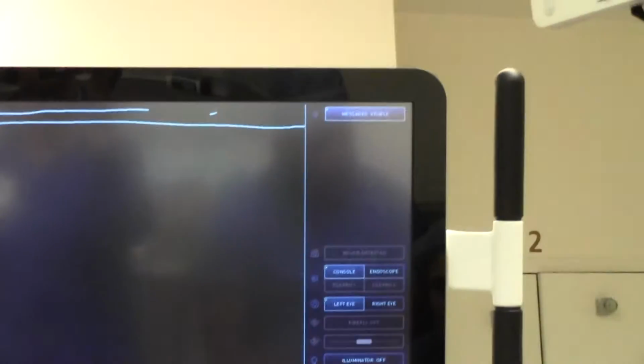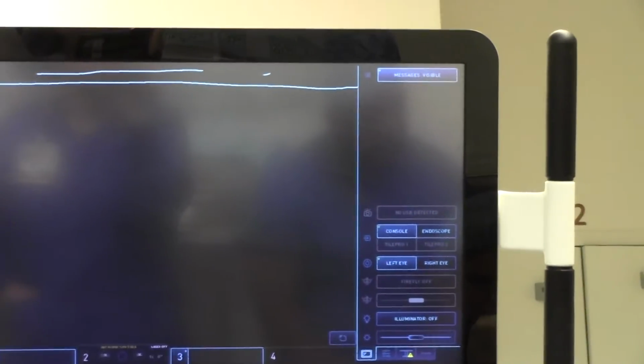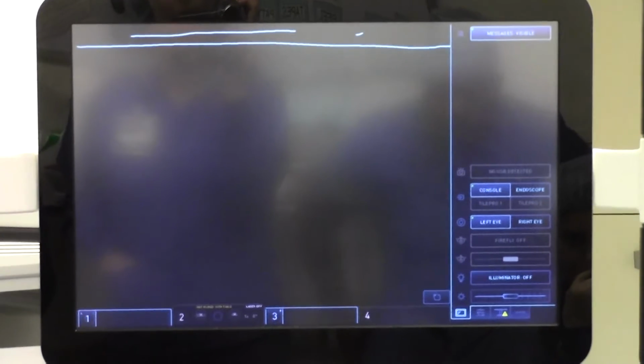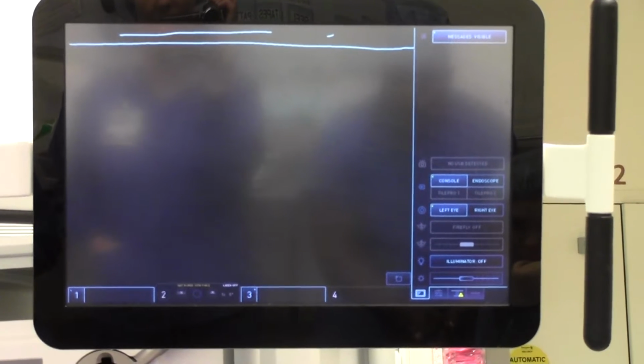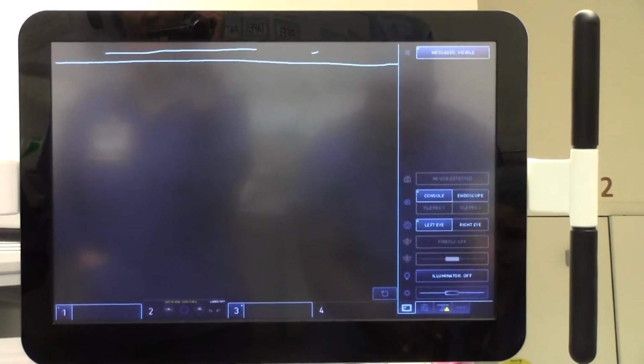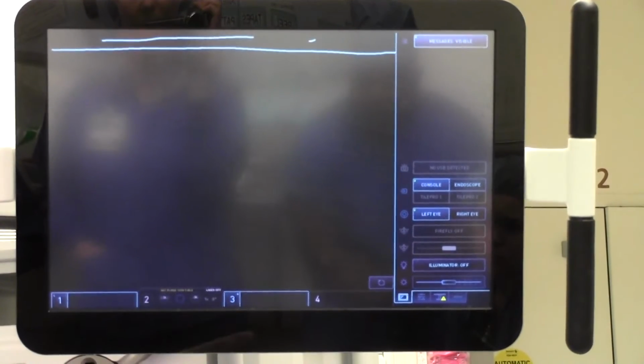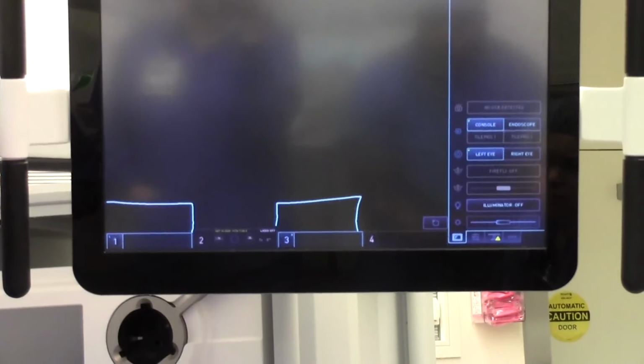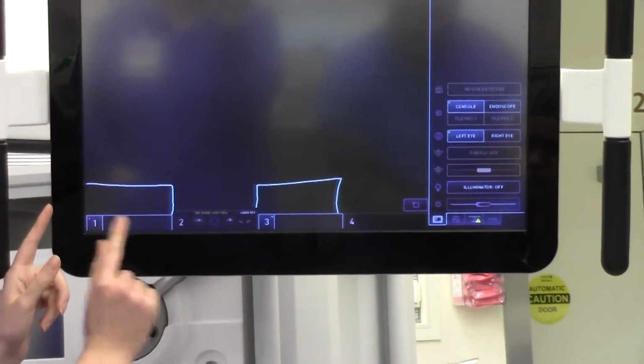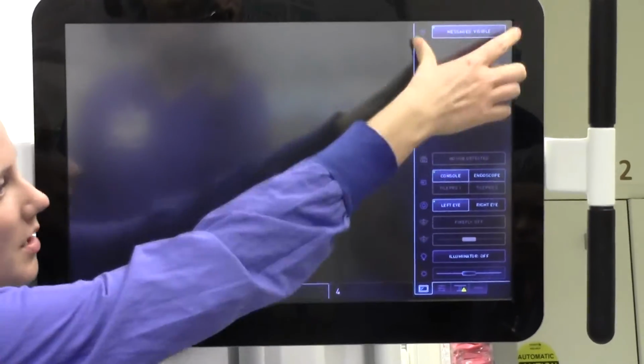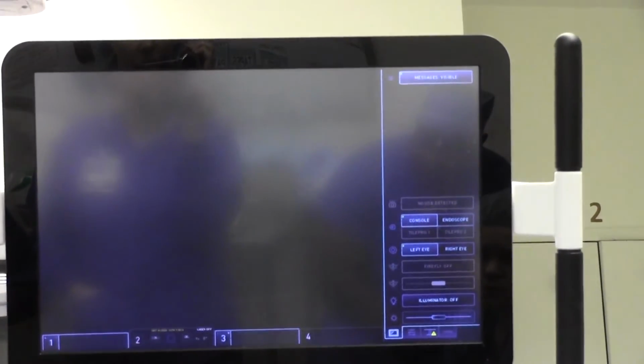Okay? So do messages at the top always refer to around the room and at the bottom always refer to what the surgeon's doing? You know how they come up right above like 1 and 3? The messages at the top tend to be system-wide messages. So it's like the blue fiber cables all need cleaning, or they'll say training instruments not for human use, things that are more system-wide. Any messages that you get down here are going to be arm specific, not necessarily surgeon specific, but they'll go with the exact arm. And then the only other messages you'll get, and we'll talk about it later, is when you get a fault, it'll come up along the sidebar here. That'll be a big system-wide message as well. That's a good way of thinking of it.